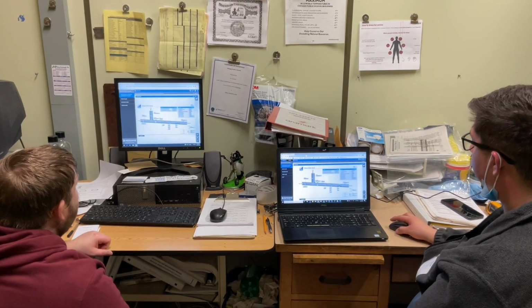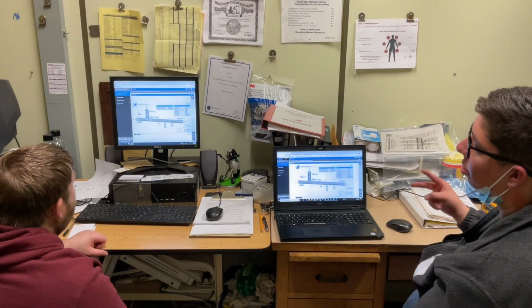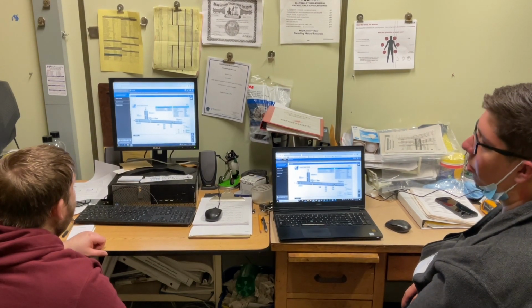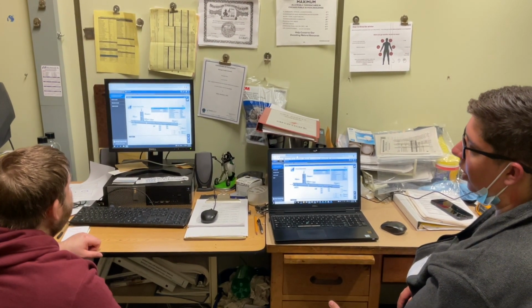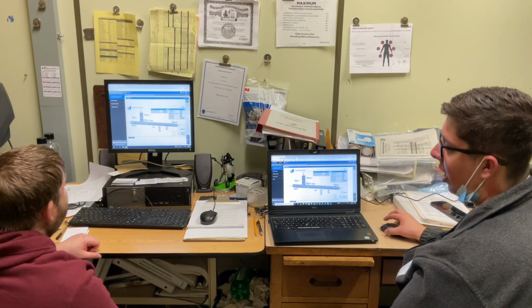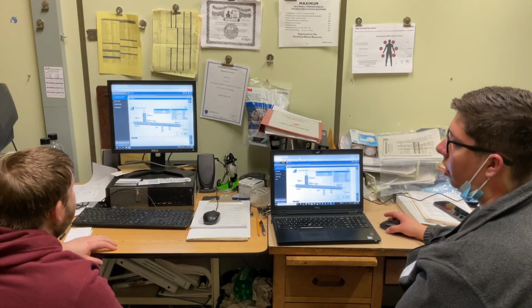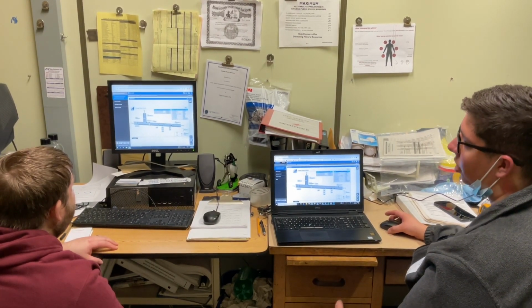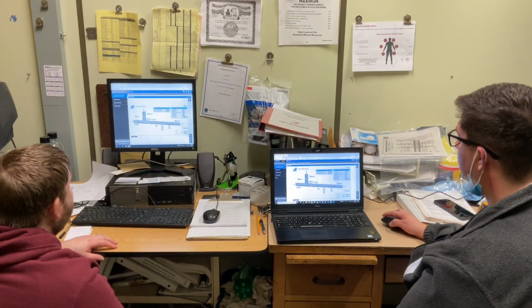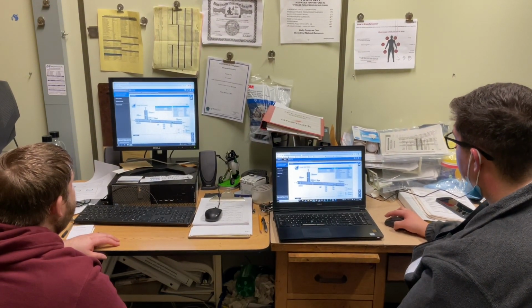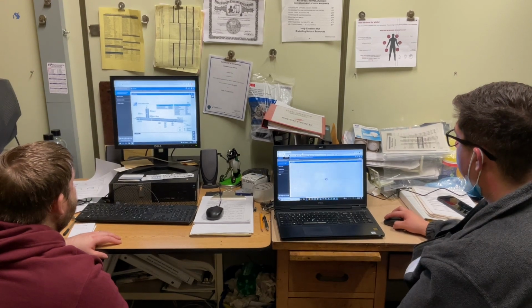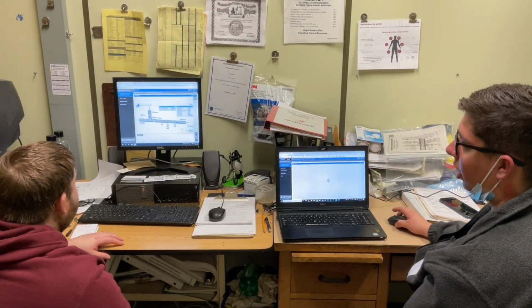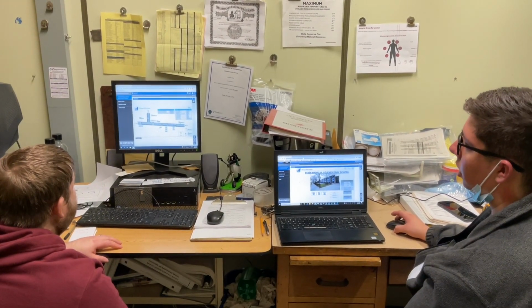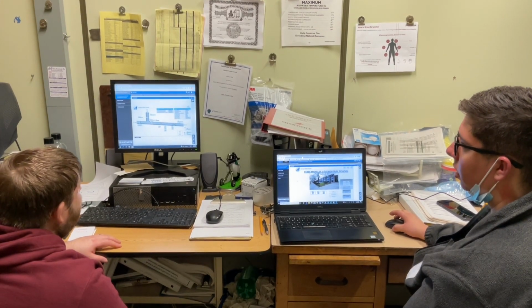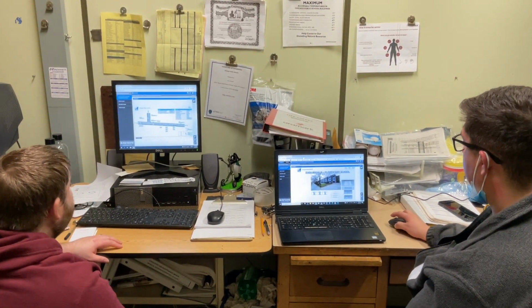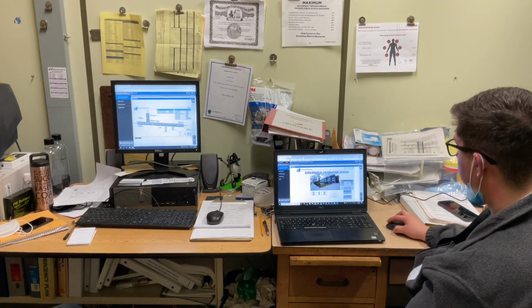This OA CO2 reset A and B, those are just the upper and lower limits. Those won't change. That's just part of the economizer too. CPS has it in there that if the CO2, the zone air quality, is too high, it'll start bringing in more OA. And those are the upper and lower limits. So there's that. I think we kind of covered everything on the univents. Are there any questions you had on the logic on those, or how they're running? I think I'm alright. Cool.